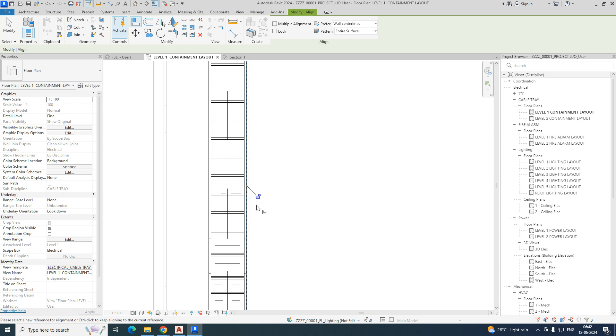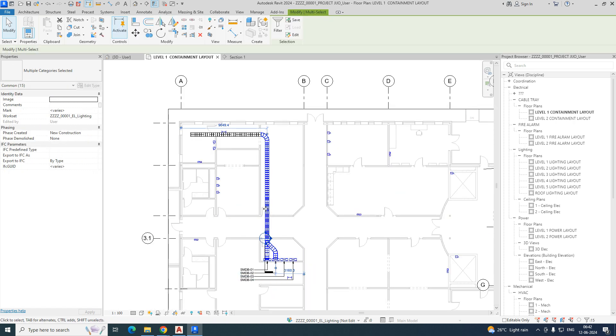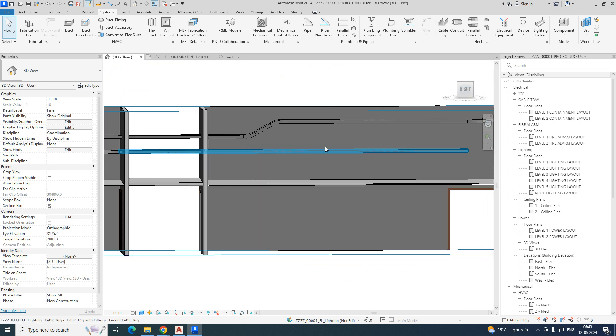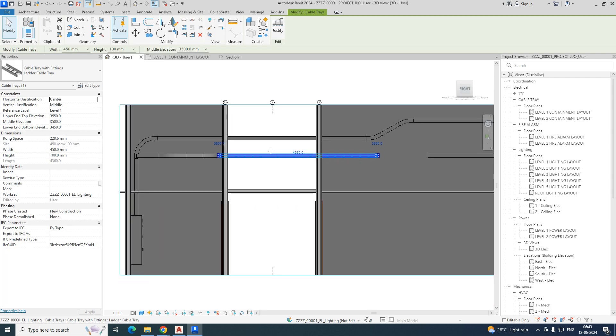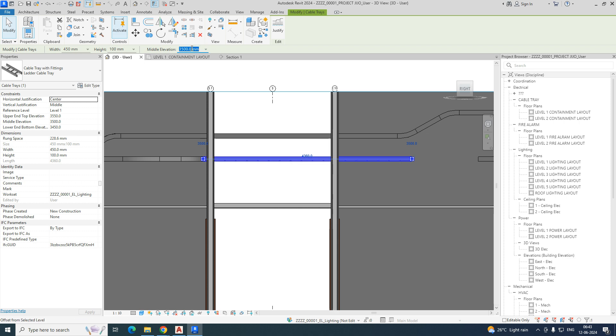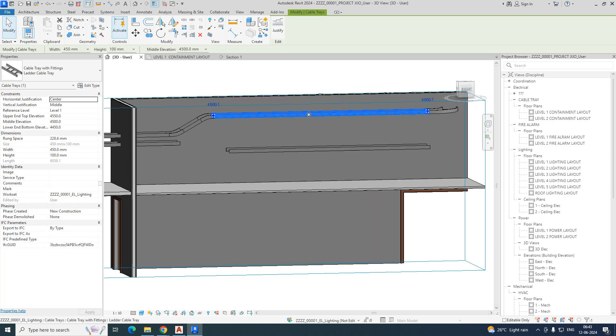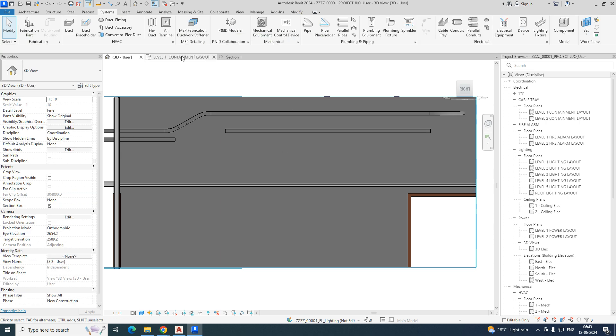Now you can see if there are any clashes — we can check in the 3D view and adjust. Selecting that, you can see it is clearly going below the first one. To run at a different height, we split it — SL is the split command. I'm giving it 3750, it will automatically adjust. This cable tray is running around 4500, so below that I'll give 4000 to maintain the gap.